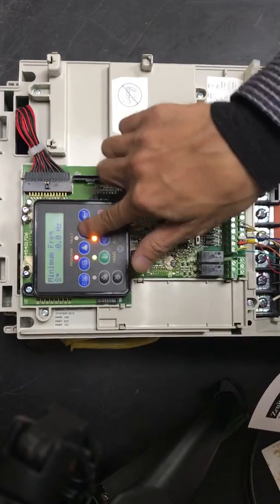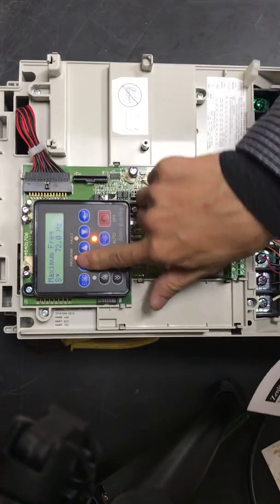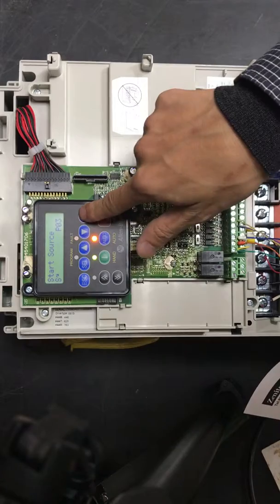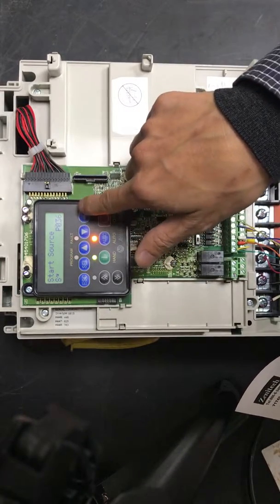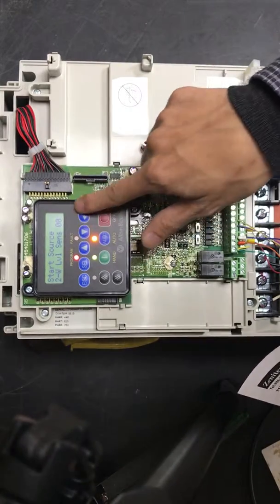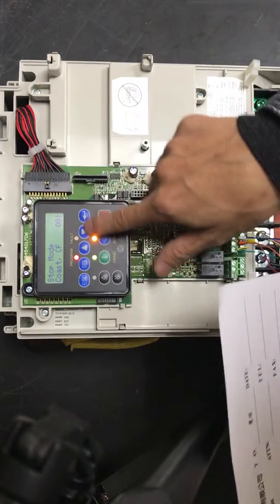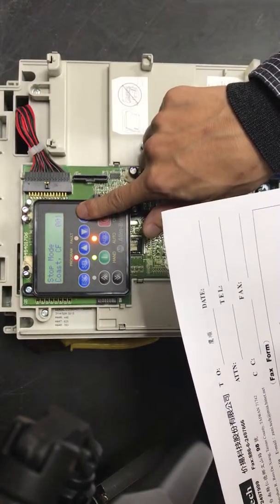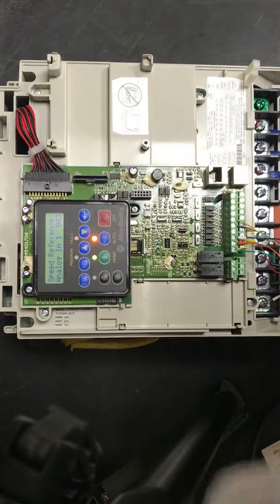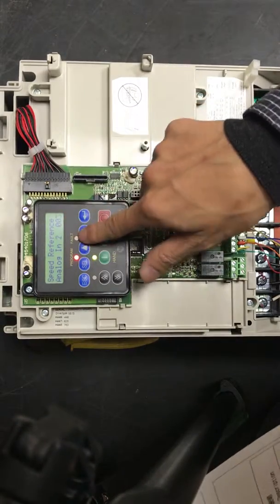Set minimum frequency to 0, press OK. Set maximum frequency to 16, press OK. P136 is the start source — change it to 3, press OK. Stop mode, change it to 1, press OK. Speed reference analog input, change it to 2, press OK.